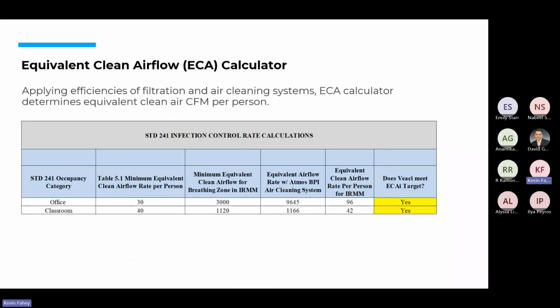So similar to what we did with the 62.1 indoor air quality procedure to show the reduction of outdoor air in a standard time, not an infection risk mitigation mode time, but how you could reduce the outside air, we've also taken this spreadsheet calculator and done something similar with the equivalent clean air to show the contribution of bipolar ionization to the equivalent clean air. And in most cases, it will show you that in an office environment or a classroom, you can reach the equivalent clean air requirements as long as you're meeting the 62.1 standard and you have technology like the bipolar ionization in addition to that. And this is all done based on testing that is required.